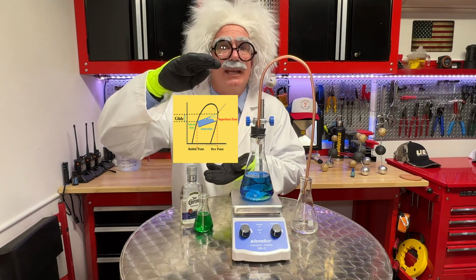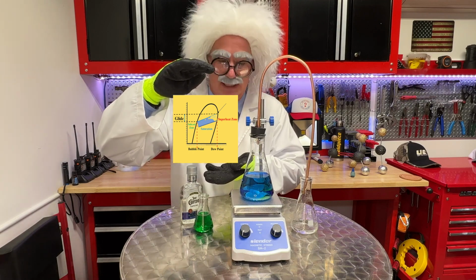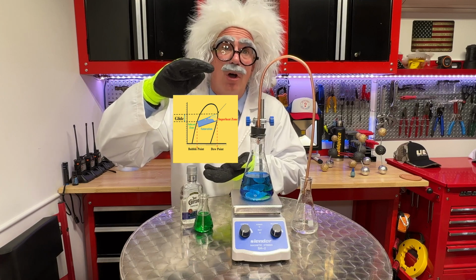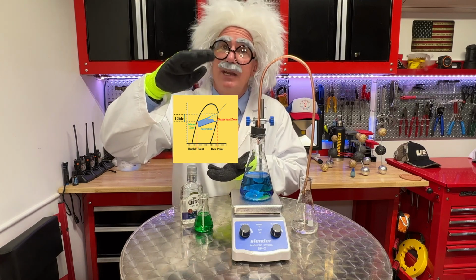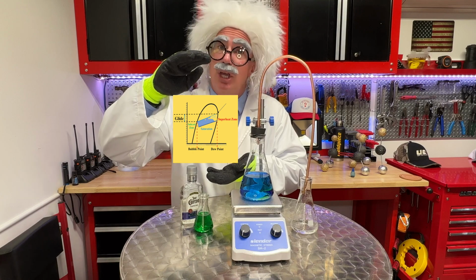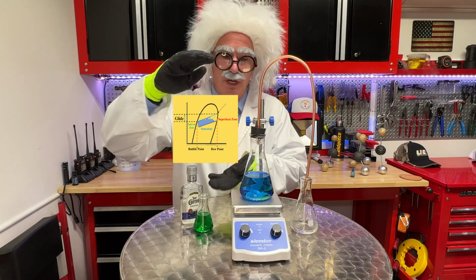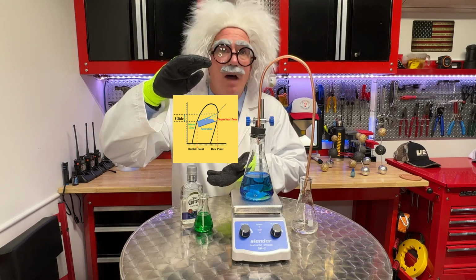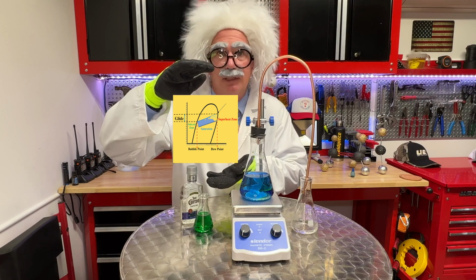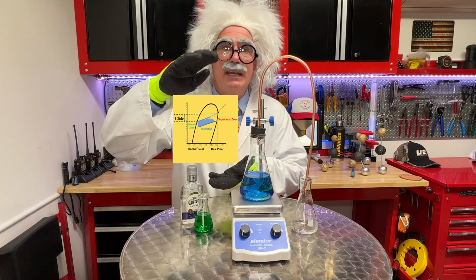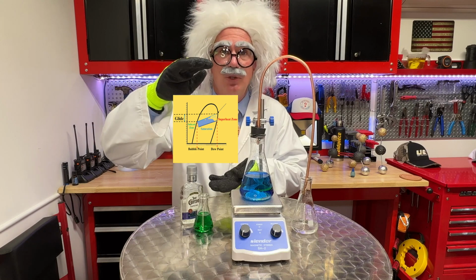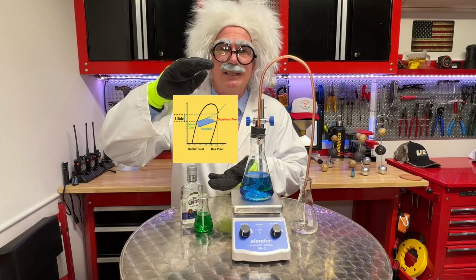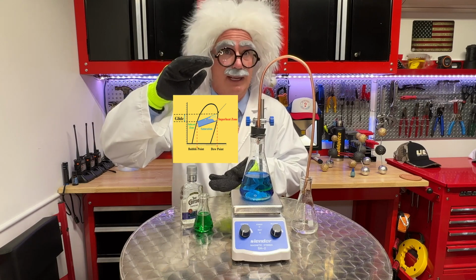And it creates a place that has two different points. It has the bottom, which we're going to call the bubble, and it creates the top that we're going to call the dew. So we know that in the middle, we can have a combination of chemicals that are in a different state. So anything above the dew is going to be vapor. So that's what we use for calculating superheat.